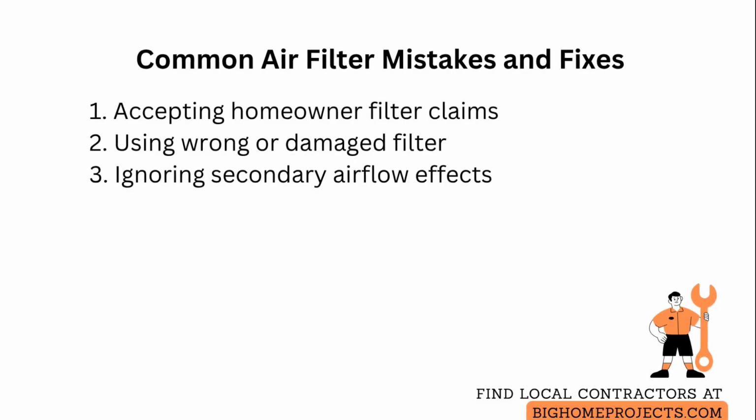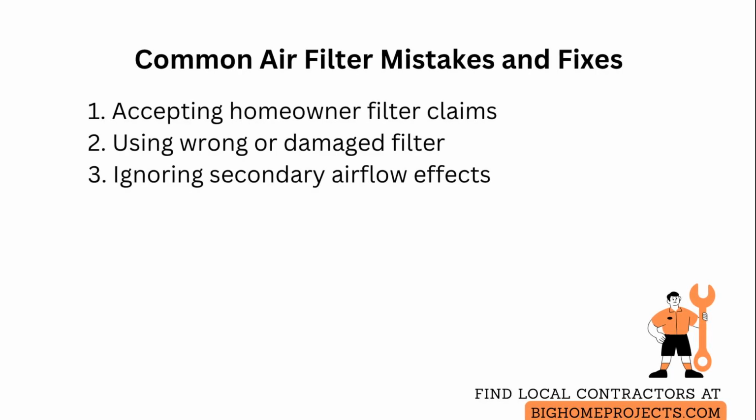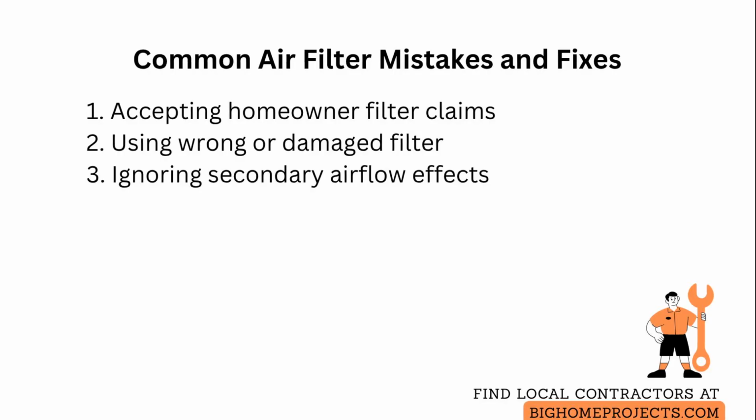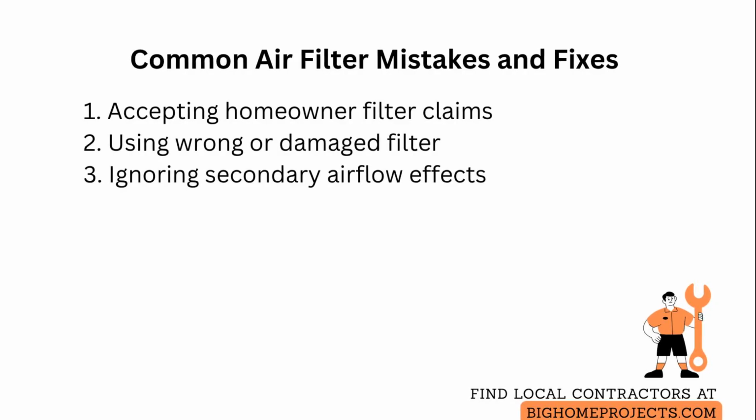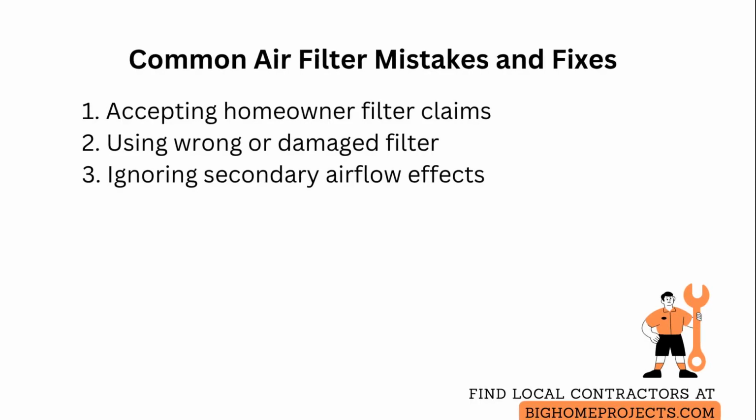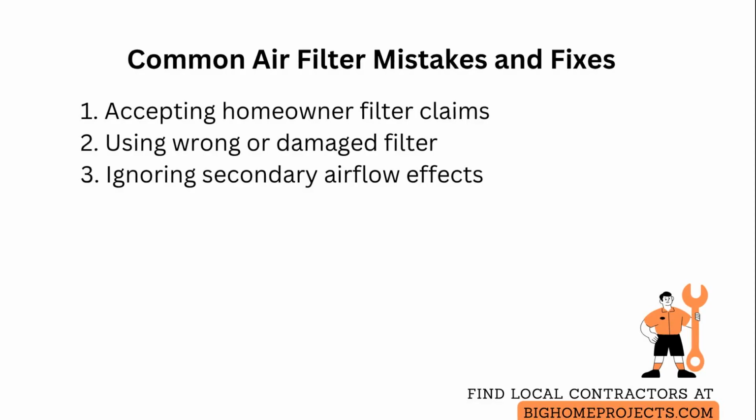Another issue is using the wrong filter type or a damaged frame, which can bypass filtration and reduce efficiency. So measure the slot and confirm the filter fits snugly and replace with the proper specification. Finally, technicians sometimes forget to check for secondary effects like restricted airflow causing frozen coils or high amperage draw. So after changing or cleaning the filter, recheck system temperatures and motor current to ensure the problem is resolved.